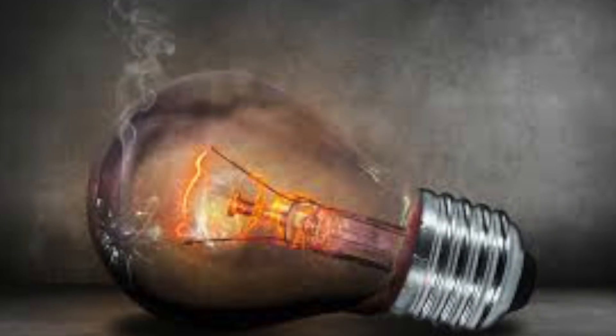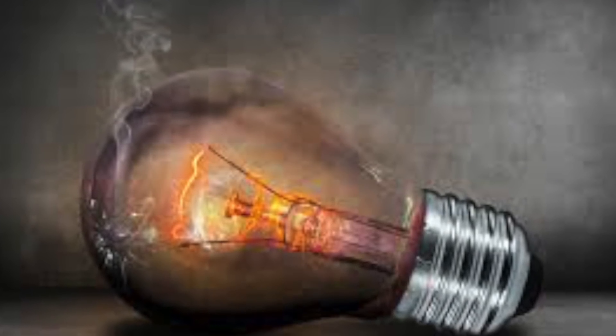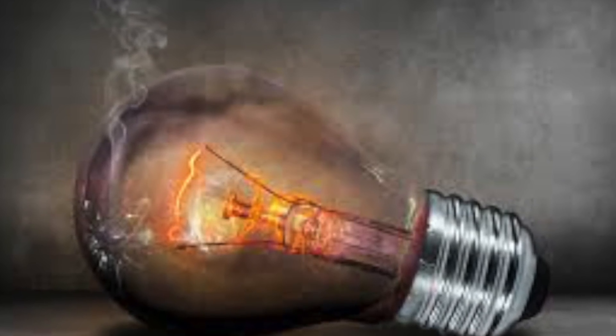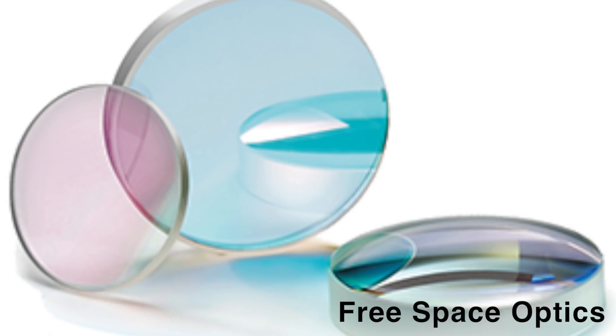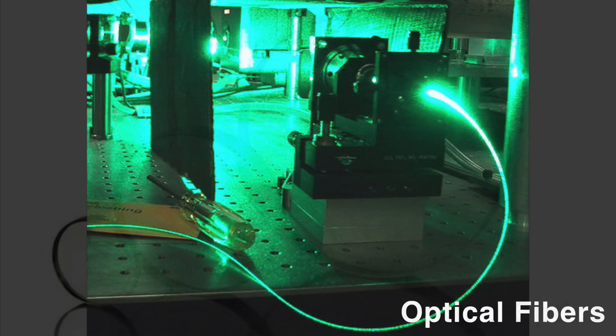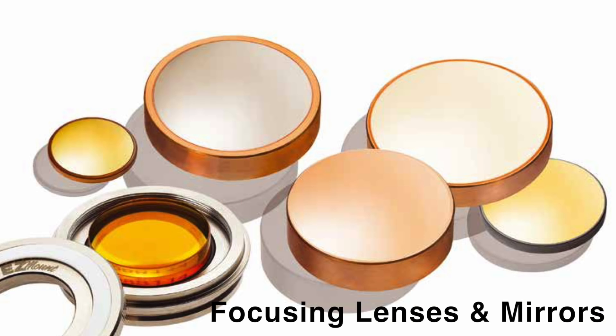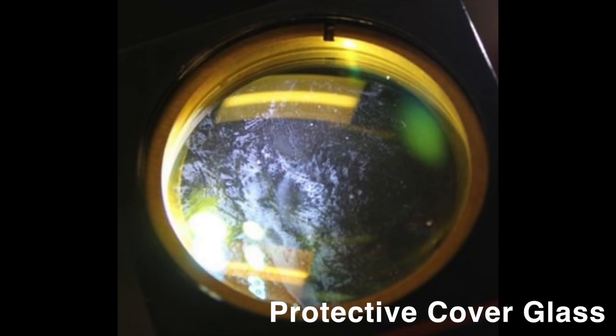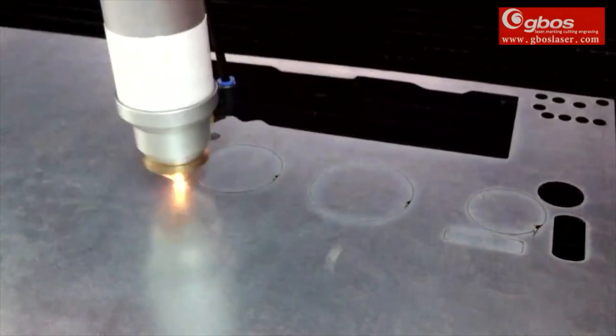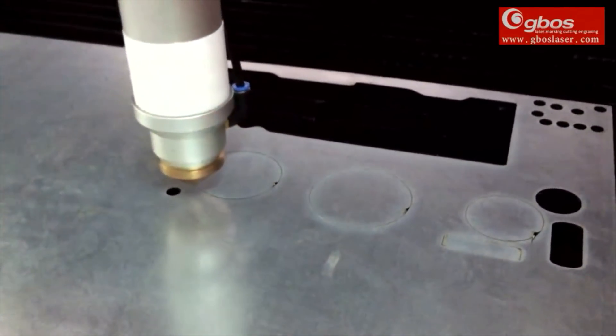A laser beam at the work surface is like a light bulb that degrades over time. Not only can the laser source degrade over time, but free space optics, optical fibers, beam shaping optics, scanning mirrors, focusing lenses and mirrors, and protective cover glass can heat up or become contaminated over time, which alters the laser beam characteristics at the work surface.